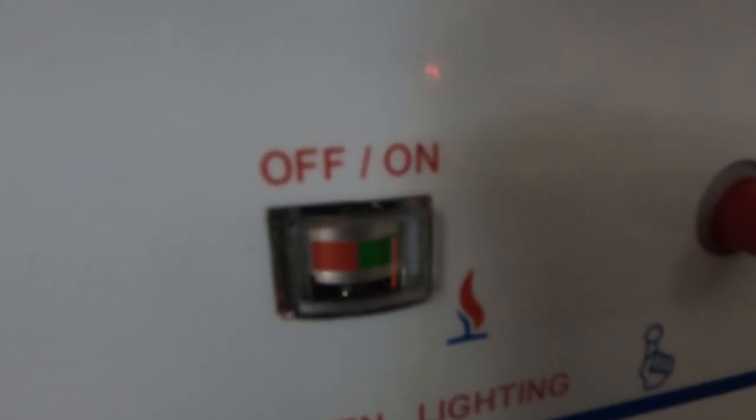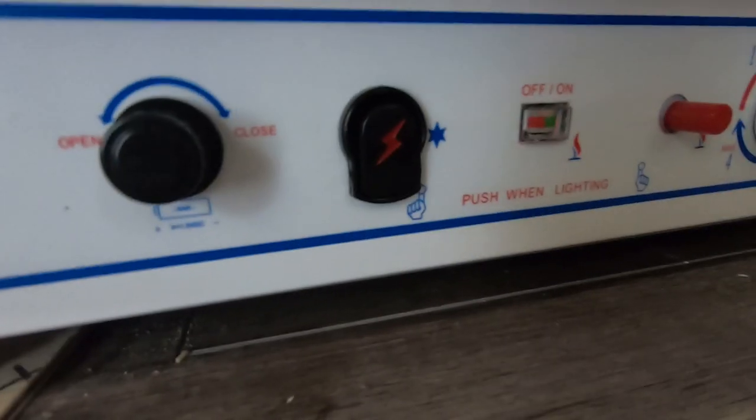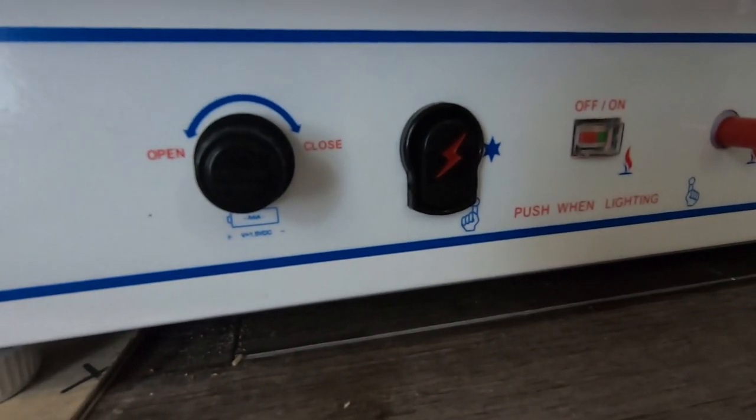It's nice that they wired it into the thermocouple instead of you just taking a guess. To check: push the button and it'll make a clicking sound. If it does not click, the battery's in backwards — see the pictogram, it shows the battery going in kind of oddly; just flip it.